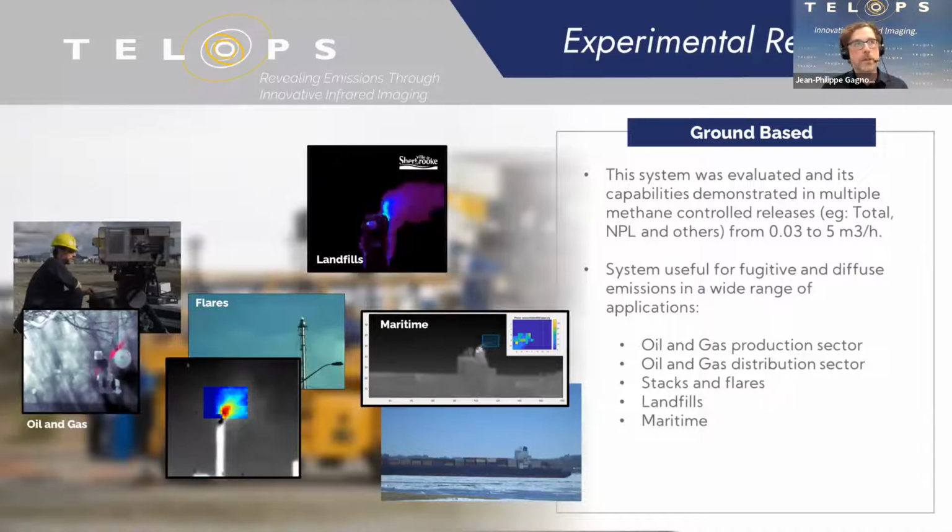Looking at flares also, either just determining the amount of unburned methane coming out of a flare, we've also tested determining combustion efficiency from flares with this technology. So it's a very safe, non-invasive way of doing the measurement. In that case, I think we were located 300 meters away from the flares.